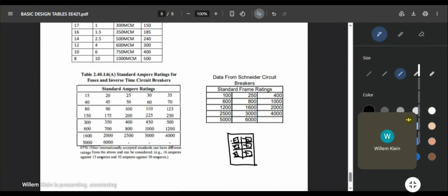Let's say you have six circuits here. Usually there's spare space here, so there's a slot for the spare. This is what I'm talking about. For the spare, you should always allot at least one to two spares on your riser diagram, on your schedule of loads, on your panel board, for expansion purposes and flexibility. Why flexibility? Because in the event that this particular slot number one gets damaged or compromised, let's say the wiring gets corroded or for some reason exposed or unsafe, you can transfer the circuit breaker or your circuit into this spare slot. Also for expansion purposes, let's say you're going to have a renovation for your building, you can use the spare for additional circuit breakers or additional circuits.